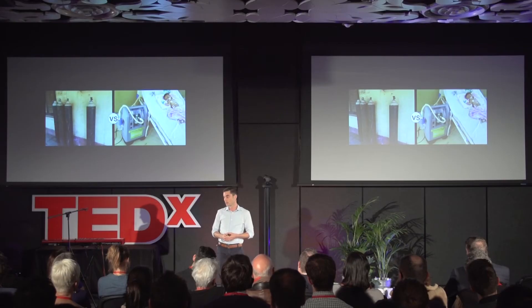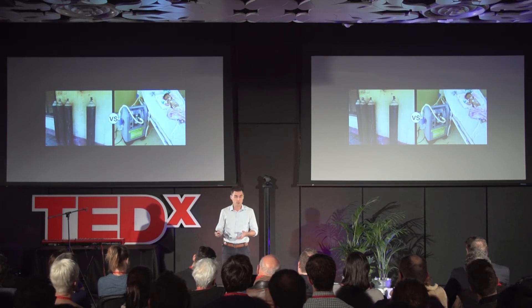So we sat down to try and work out what was going on. We found that their concentrators were not suitable for use in hot, humid, dusty Nigerian conditions. Many of them were poor quality, many were donated second-hand from abroad, many were dead on arrival. Concentrators were flogged until they died with no routine maintenance and no way of doing repairs or even getting spare parts. By understanding how concentrators were actually used in this particular environment, we were able to work together to improve the system.